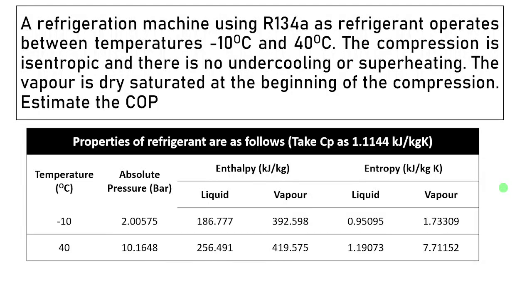A refrigeration machine using R134A as a refrigerant operates between temperatures minus 10 degree centigrade and 40 degree centigrade. The compression is isentropic and there is no undercooling or superheating. The vapor is dry saturated at the beginning of the compression. Estimate the COP. This is the question and the properties table is given along with the CP value.